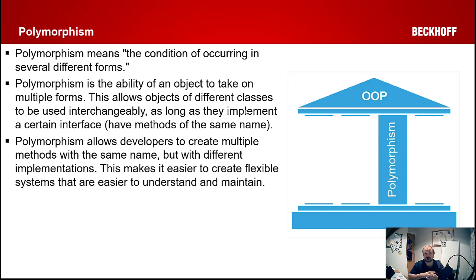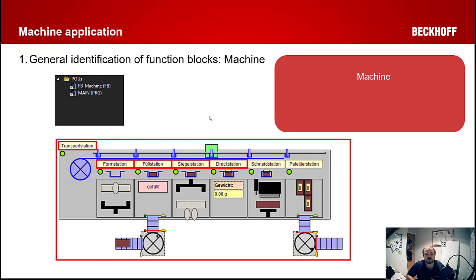So let's now apply those things to an OOP framework implementation. We'd have our main machine at the top level, so we would encapsulate all of the data and all of the functionality of our machine into this one class that effectively has overall global control of our machine. It also maintains a state, whether that could be like a PackML state for example, and maintains all the data about the machine that can then be exported to HMI and so on. Now it doesn't care what the other sub-components do or how they work. All it needs to be able to do is interact with and extract data from them.